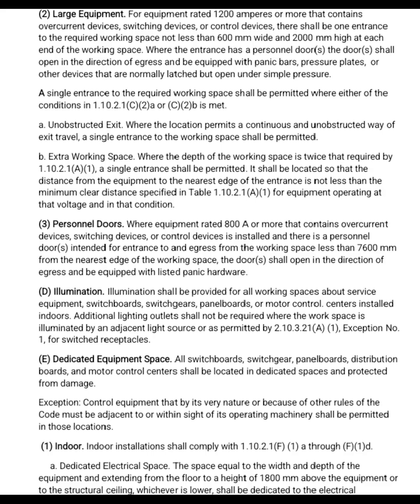A. Dedicated electrical space. The space equal to the width and depth of the equipment and extending from the floor to a height of 1,800 mm above the equipment or to the structural ceiling, whichever is lower, shall be dedicated to the electrical. Large equipment indicates that if the electrical equipment is very large, the work area in front of it must have at least one entrance. The 600 mm must be 2 feet wide and the 2000 mm must be 6.5 feet high.